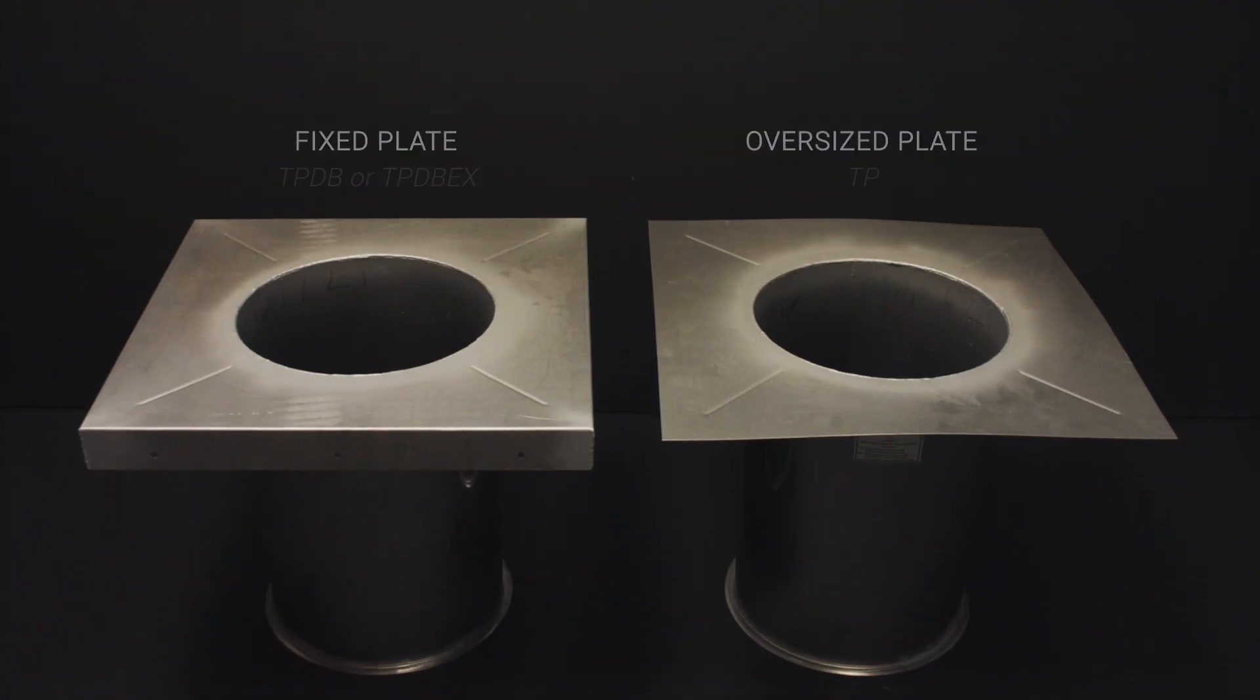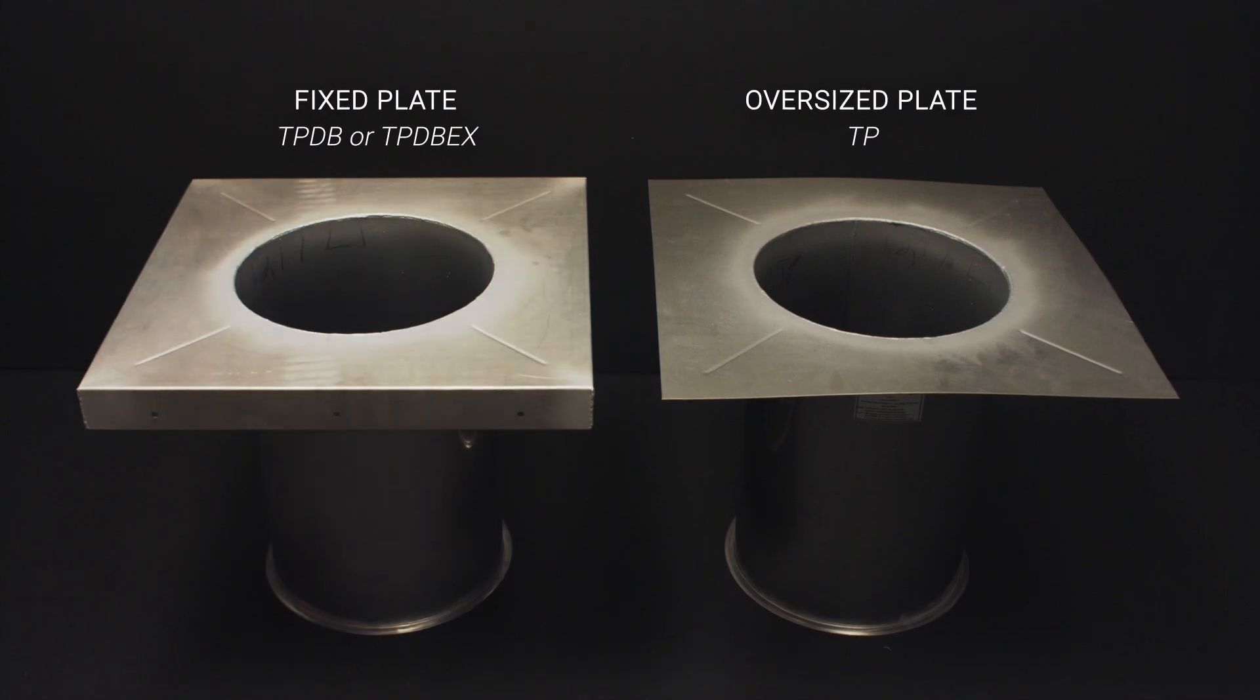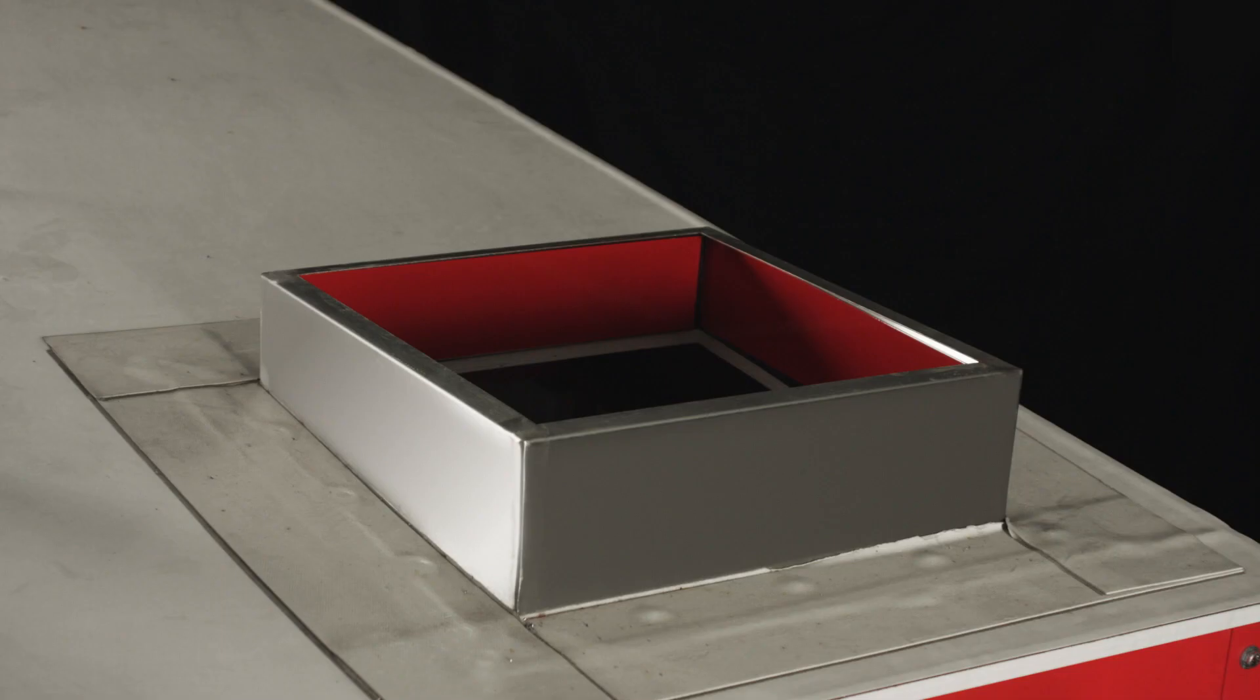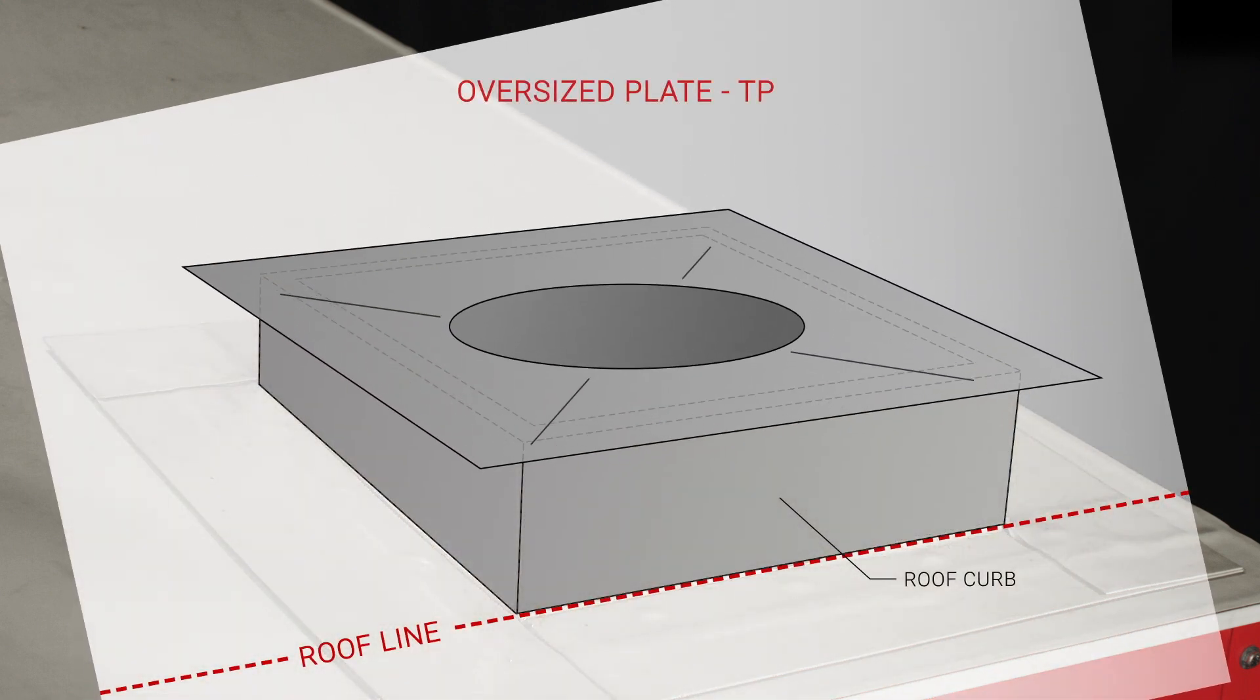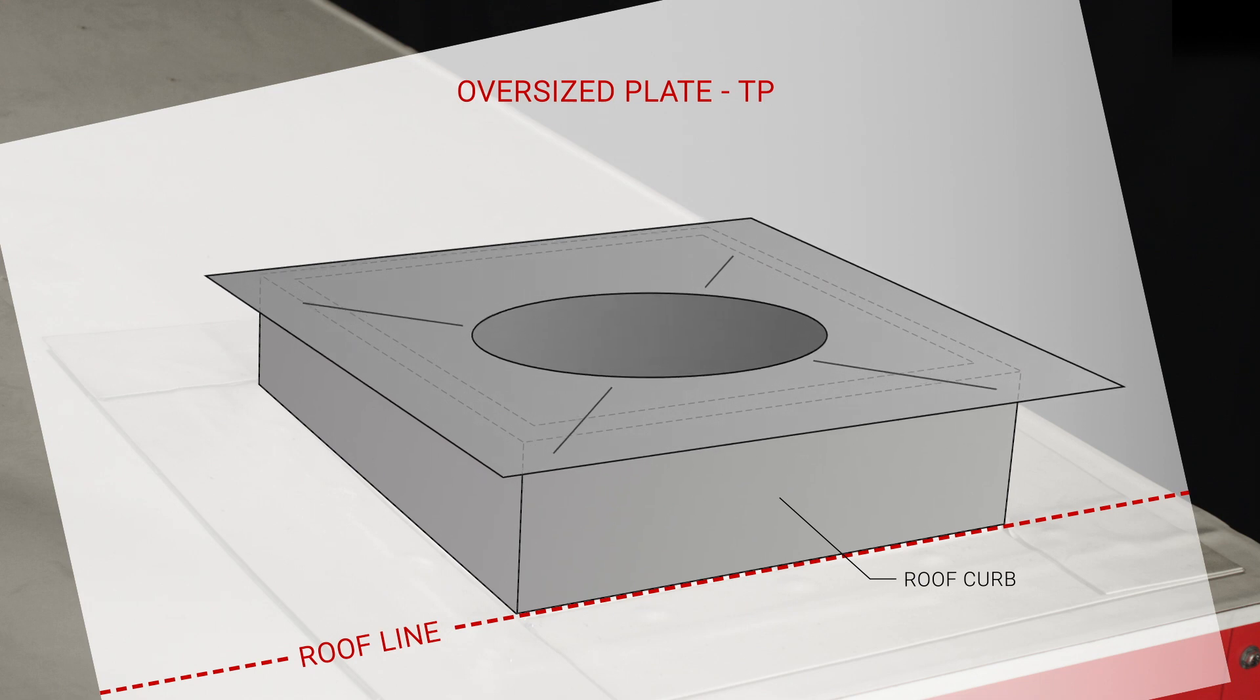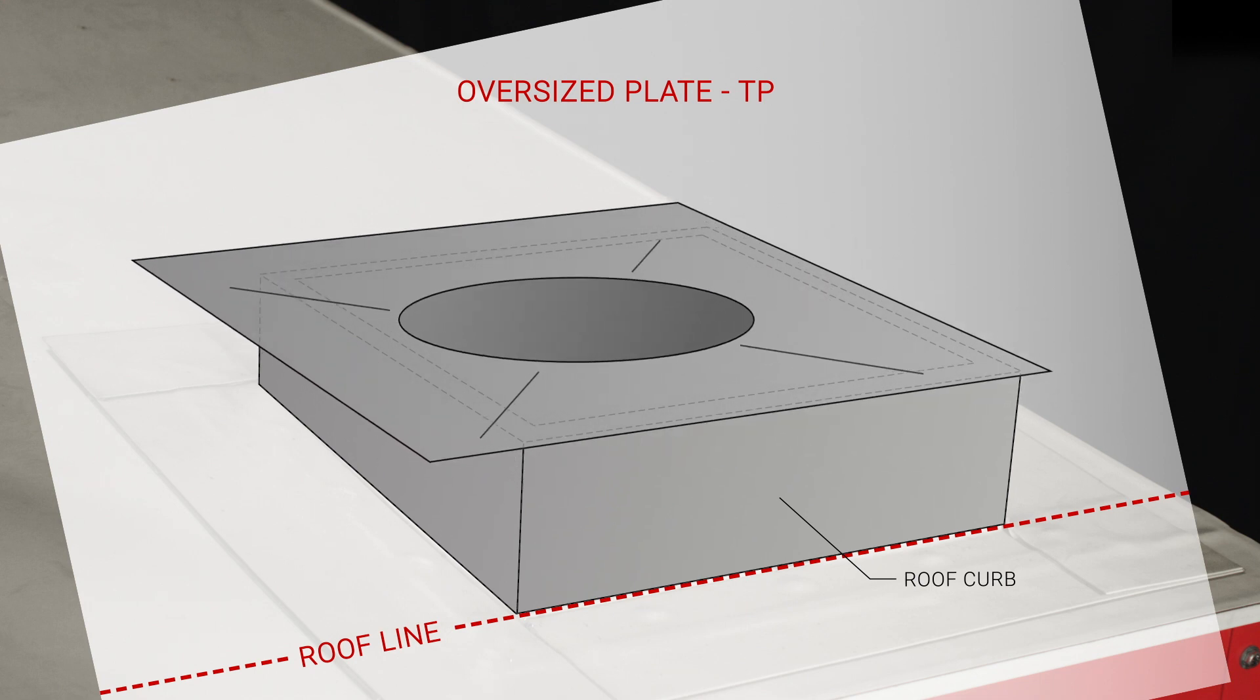There are two categories of transition plates, either fixed or oversized. To install an oversized TP plate, first place it on the curb. The plate can be positioned off-center with the curb, provided that the minimum clearance to combustibles is maintained.